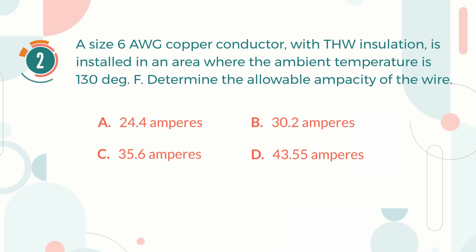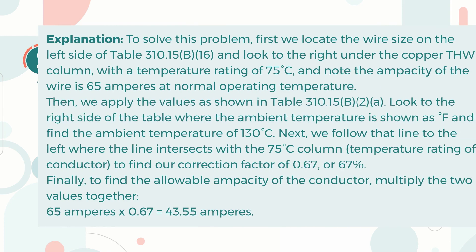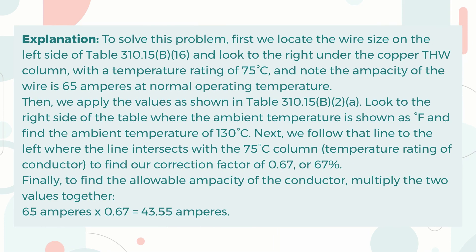The correct answer is D. 43.55 Amperes. Explanation: To solve this problem, first we locate the wire size on the left side of Table 310.15(B)(16) and look to the right under the copper THW column, with a temperature rating of 75 degrees Celsius, and note the ampacity of the wire is 65 Amperes at normal operating temperature.